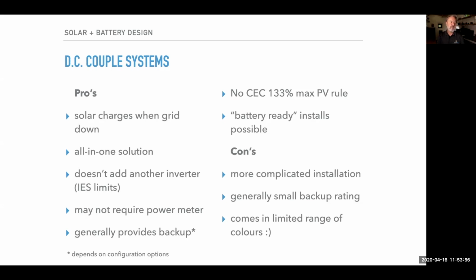Now, for those who are not familiar with the Clean Energy Council in Australia, to access government rebates we are required to comply with the CEC guidelines. They have in their guidelines a slightly perverse rule, which is that the maximum PV size compared to the AC output of an inverter is 133%. That means if you've got a 5 kilowatt inverter, you can't put in more than 6.6 kilowatts of solar on that inverter if you don't have batteries. And that's the real limit on oversizing. But anyway, DC coupled systems, because they've got a battery, aren't affected by this, so you can actually oversize a lot more. It is also possible with DC coupled systems to have a battery-ready install. That means it works as a grid-tie, grid connect inverter even without batteries, and the batteries can be added later.